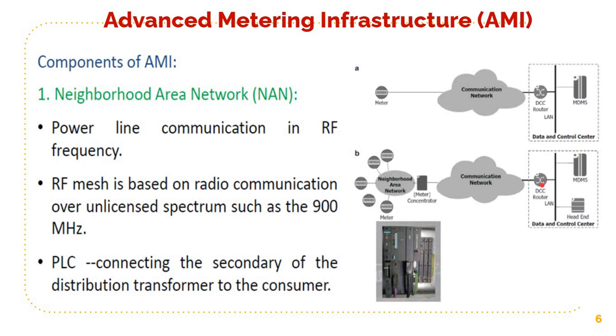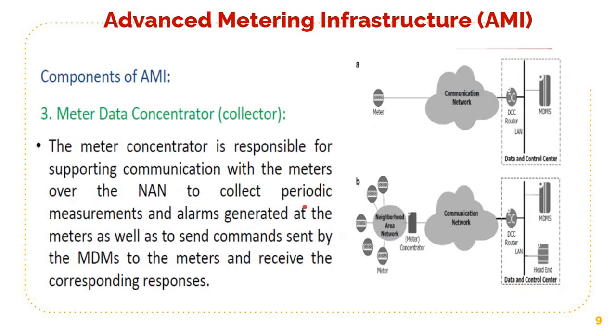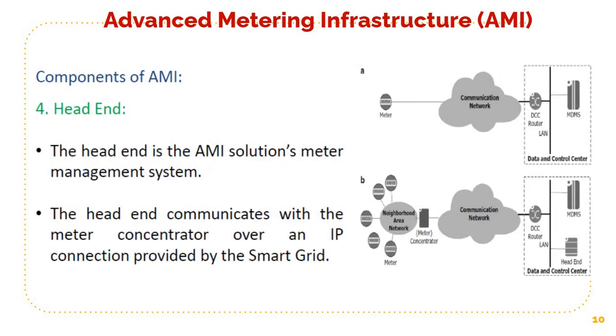From the DCC router, through the LAN, it reaches the MDMS — Meter Data Management System. Secondly, smart meters. These meters should support a communication interface so that they can be connected to the NAN. A meter data concentrator, or collector, is responsible for supporting communication with the meters over the NAN, to collect periodic measurements and alarms generated at the meters, as well as to send commands from the MDMS to the meters and receive the corresponding responses. Finally, the headend is the AMI solution's meter management system. It communicates with the meter concentrator over an IP connection provided by the Smart Grid.